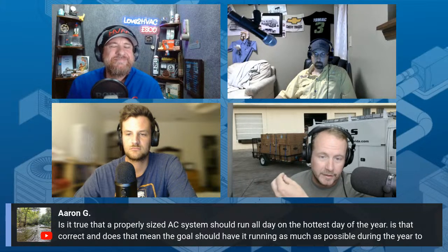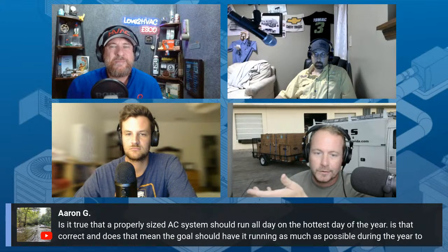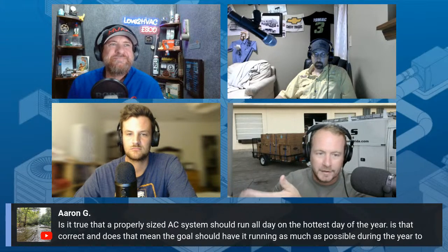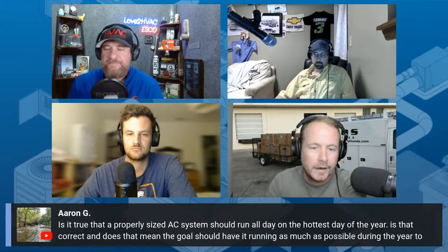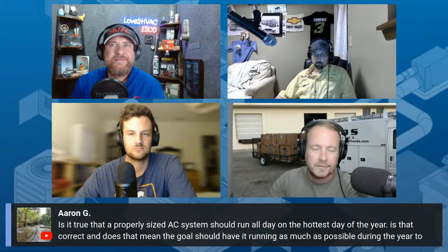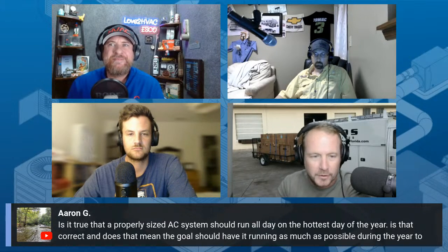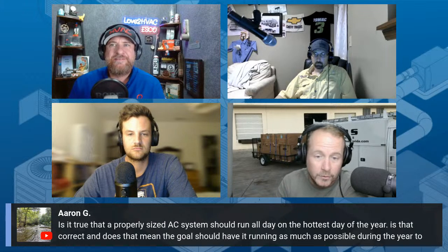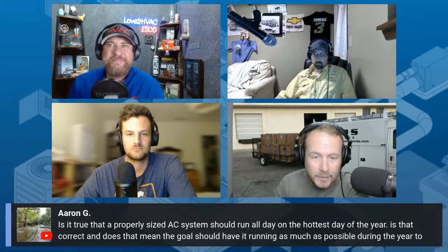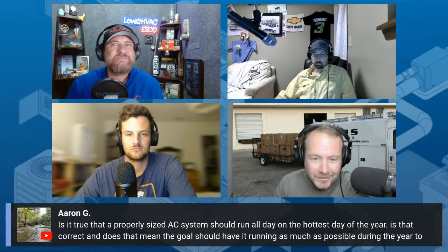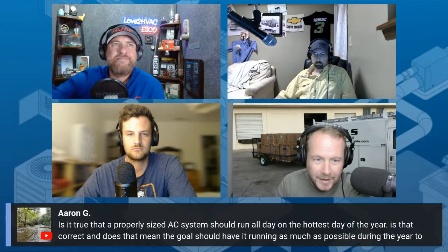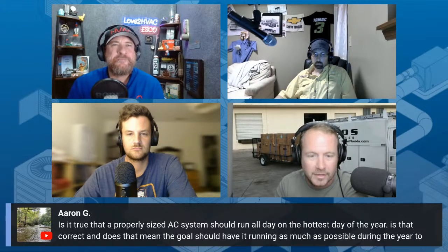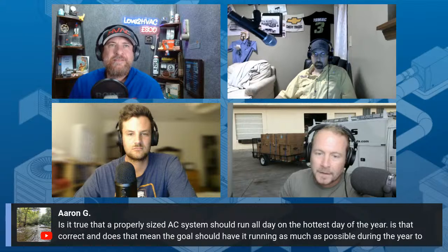If you do things like put in a whole home dehumidifier to help deal with the latent load during shoulder seasons, and you use that as part of your strategy, you can get away with oversizing more. In commercial, they oversize all the time, but they use other strategies, additional dehumidification capacity, DOAS units, and other things to help deal with it. But the answer in residential is you don't want to oversize.